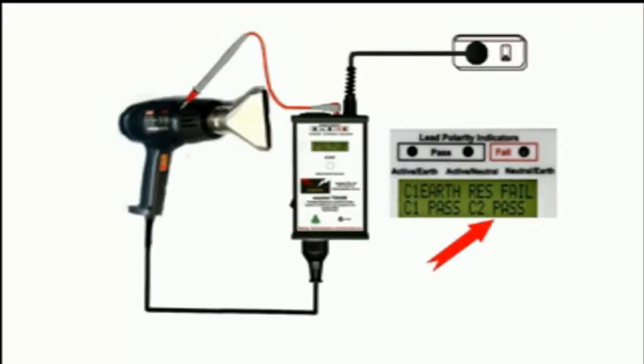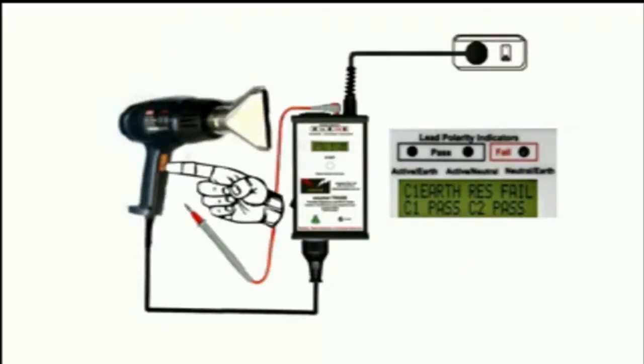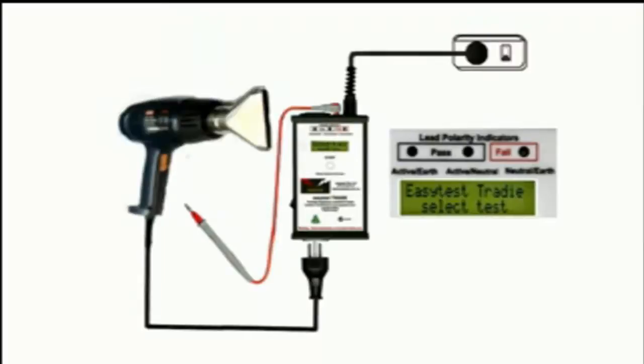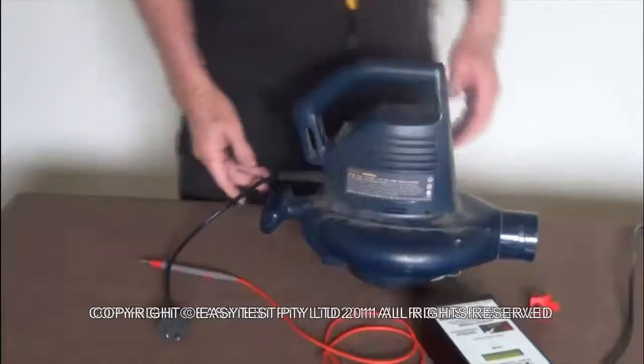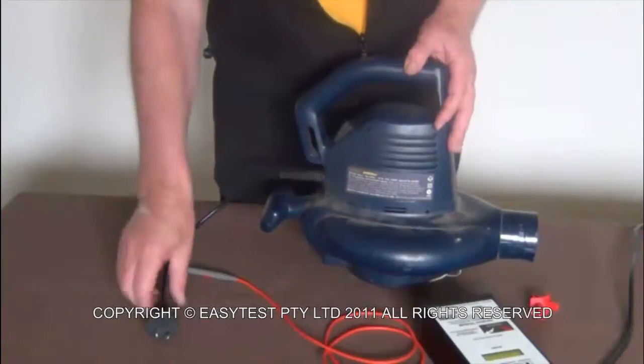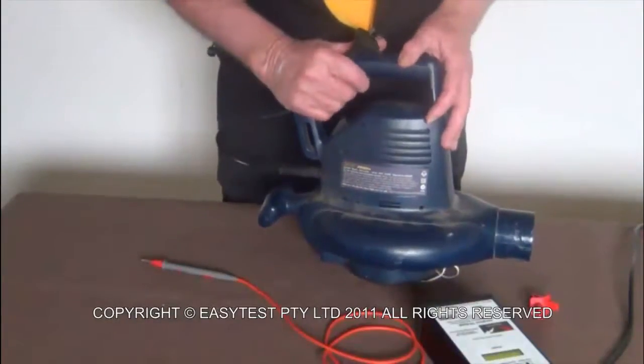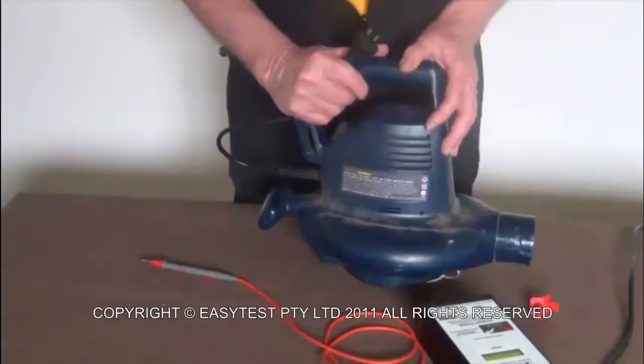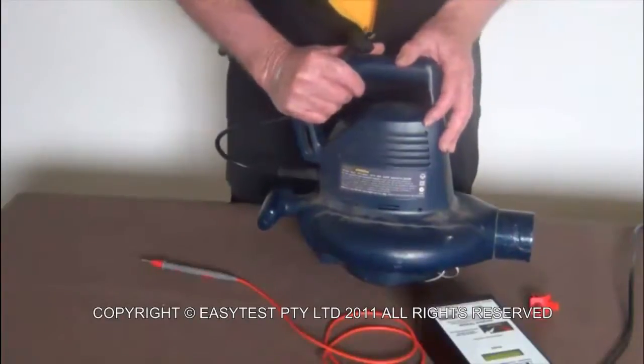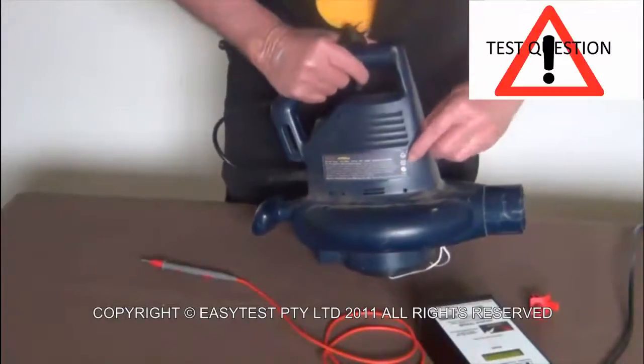Unclip the test probe and check any other bits of exposed metal that might possibly be live. As long as we have a C2 pass, there's no leakage current and the test is completed. It really is that easy. Switch it all off, unplug it and tag it. Right, this time we'll look at some Class 2 equipment. You'll recall that Class 2 has 2 layers of insulation and no earth wire. It's identified by the double square symbol.